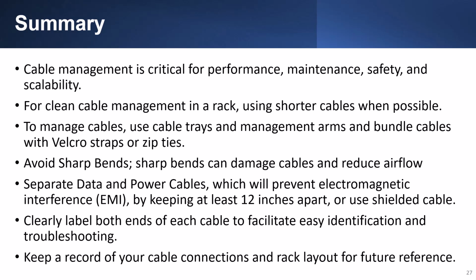Separate data and power cables to prevent electromagnetic interference, or EMI, by keeping them at least 12 inches apart, or use shielded cable. Clearly label both ends of each cable to facilitate easy identification and troubleshooting, and keep a record of your cable connections and rack layout for future reference.